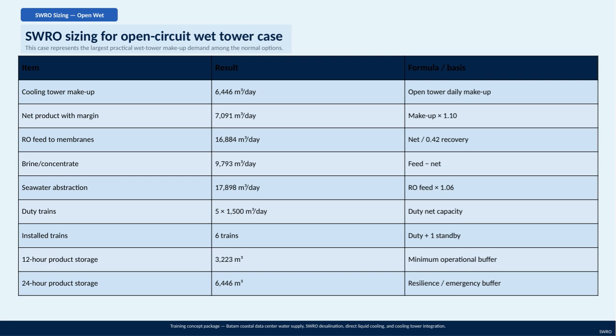The system is designed with 6 trains of treatment capacity, 5 actively running, each capable of producing 1,500 cubic meters per day, and 1 held in standby for reliability. Finally, to maintain operational stability and provide emergency resilience, the system includes storage buffers equivalent to 12 and 24 hours production, holding 3,223 and 6,446 cubic meters, respectively. This comprehensive sizing ensures continuous, reliable water supply for the Batam Coastal Data Center's cooling and desalination needs.